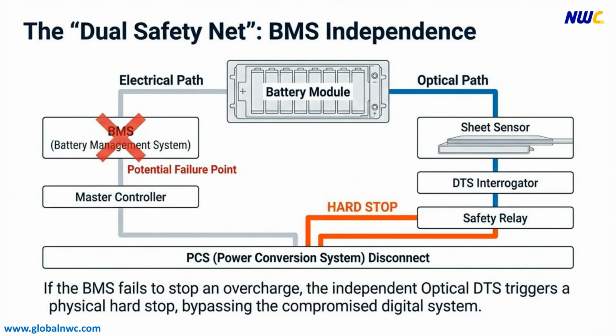To address potential failures in the electrical pathway of the BMS, we have implemented a dual-layer safety architecture using an independent optical pathway. Even if the BMS fails, the optical DTS system can immediately trigger a physical hard stop, securely shutting down the power conversion system. By introducing this independent optical safety layer, the system overcomes the inherent limitations of digital control systems and delivers hardware-level reliability. This represents a next-generation safety solution for critical battery and energy systems.